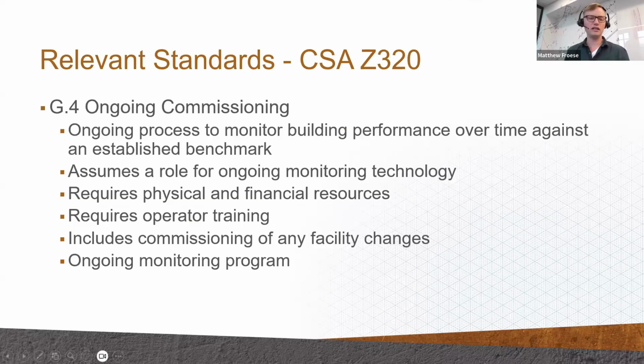So this ongoing commissioning process always assumes this kind of role of ongoing monitoring technology, but it can't ever just be a technology piece. You've got to have the physical and financial resources to back it up. You've got to have an operator who's ready to respond and has the staffing and resourcing to say, hey, if this sequence says this VAV is broken, do I have somebody who can go look at it and fix it and get parts? All that practical stuff still has to be there.